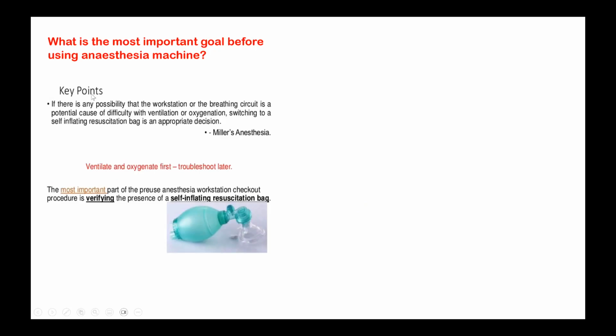What is the most important goal before using an anesthesia machine? Machine check. No, sir, ambu bag. The key points are you should see whether you have an ambu bag available and make sure that it is in working condition. And trace the path of the gases and vapors from the origin to the patient. Where is it delivered to the theater? How is it delivered to the machine? And once it is delivered to the machine, what changes happen?